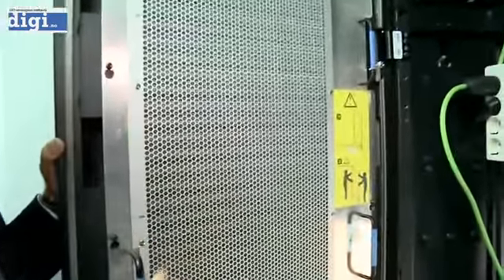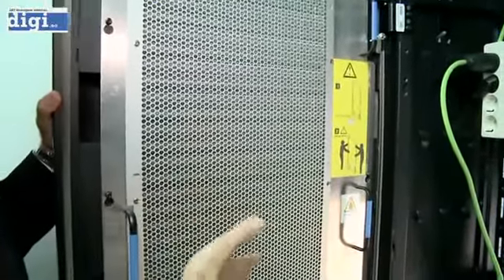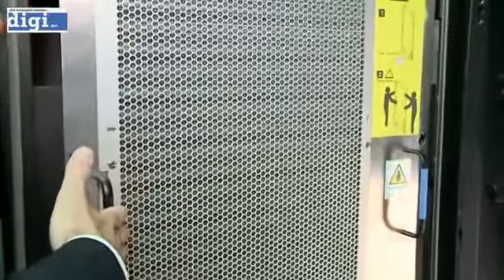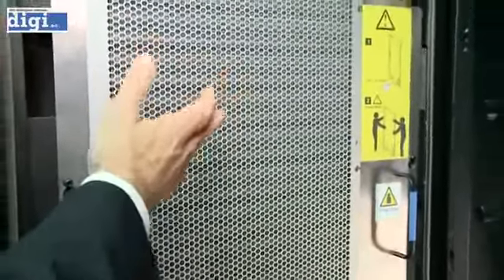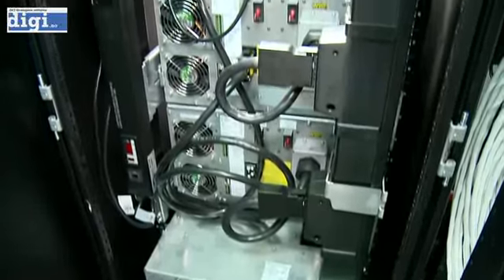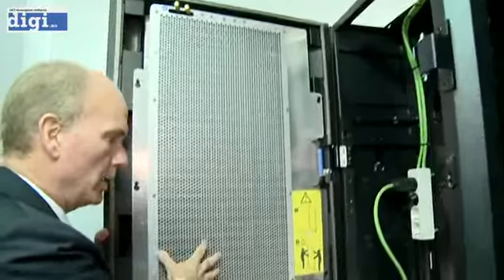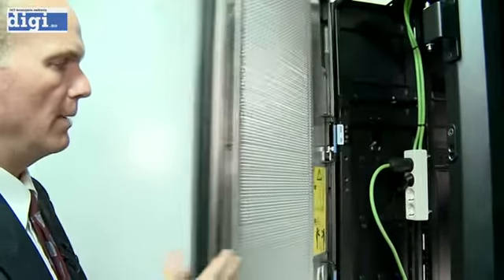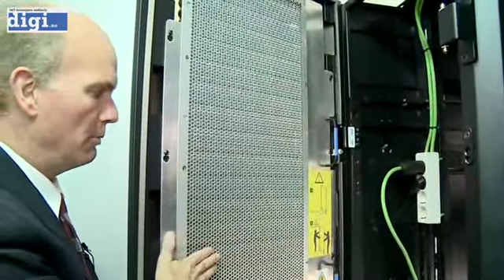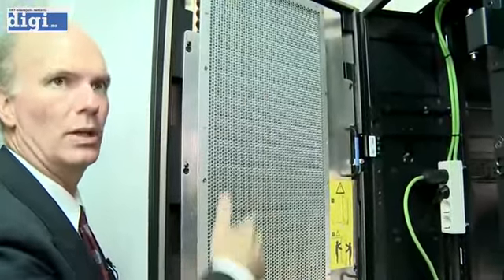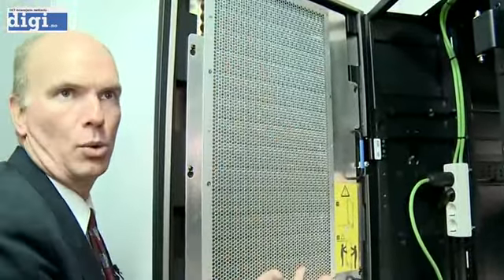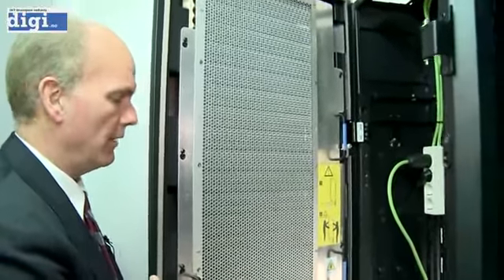It's basically a chilled water loop, like a radiator system. There are no moving parts, it requires no electricity, no service, no maintenance, and no noise - no fans. The server fans push the hot air back through this low-resistance coil, which removes all the heat. When the door is closed and operating, the air coming out the back is actually cooler than the air going in the front, so it's very energy efficient and effective. We can put these on every rack within the container as the total cooling solution, or supplement it with overhead fan coil units or in-row cooling units. We have different options, but it's a very efficient, effective solution.